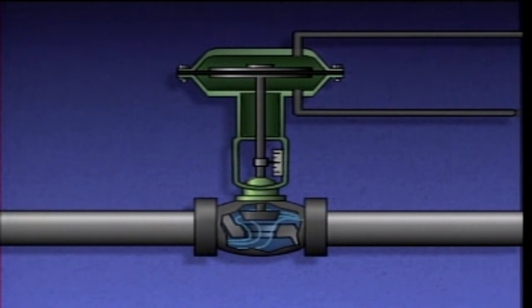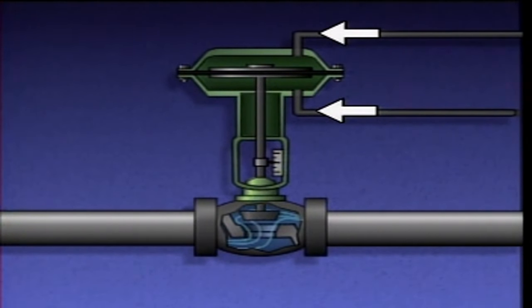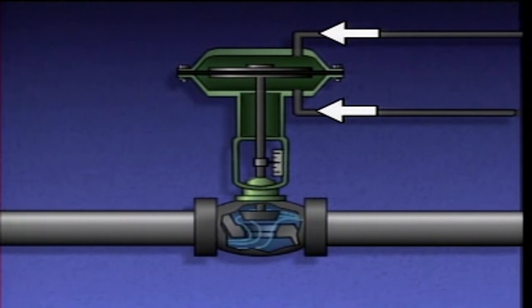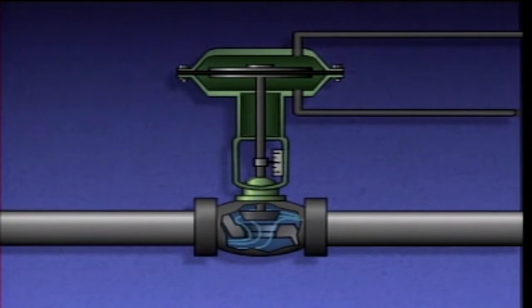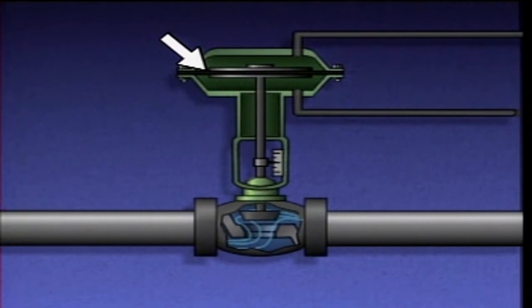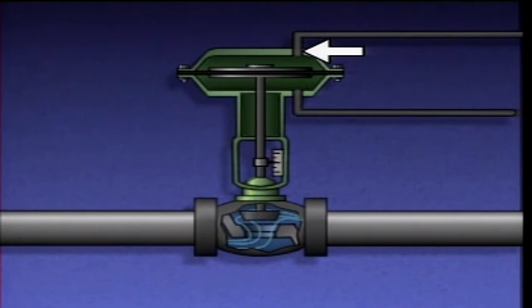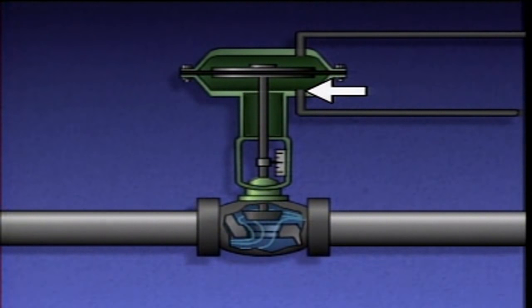A double-acting diaphragm actuator is called double-acting because air pressure acts on both sides of a flexible diaphragm to position a valve. A double-acting diaphragm actuator consists of a casing, a flexible diaphragm, an upper air supply port, and a lower air supply port.